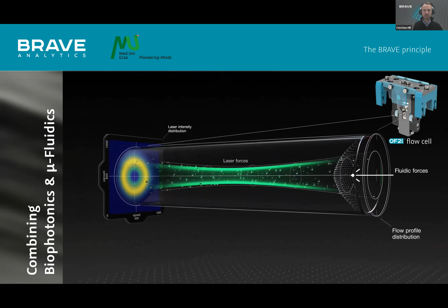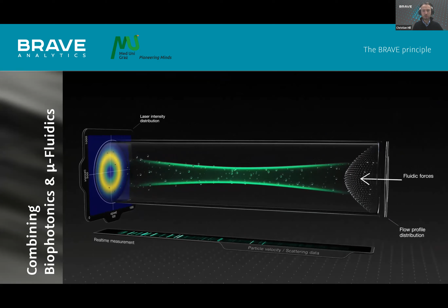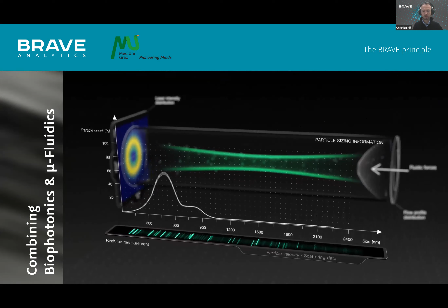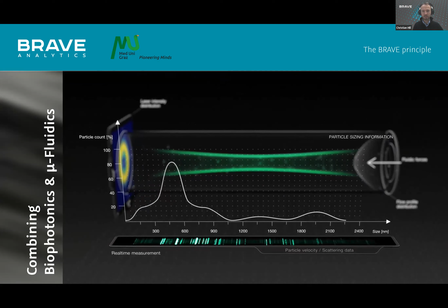How do we do it? We have this new approach called optofluidic force induction, OF2I. We combine biophotonics and microfluidics. We pump the fluid containing the particles through our measuring cell, and we introduce a laser. This laser has a couple of tasks. It first makes the particles visible, but it also changes the trajectories. The trajectories are changed by photon momentum transfer as a new approach, and we watch the particles, how they flow through our measuring cell and how they scatter light. And all this can be used for continuous feedback, for real-time online nanoparticle characterization.